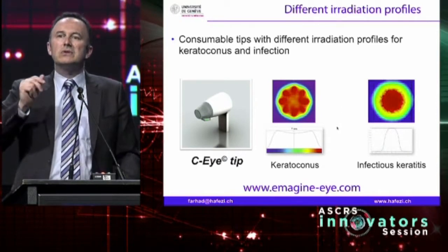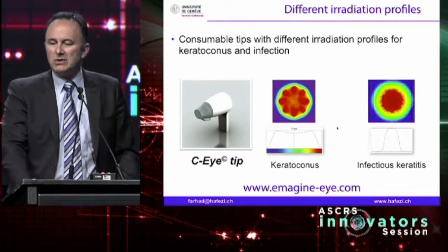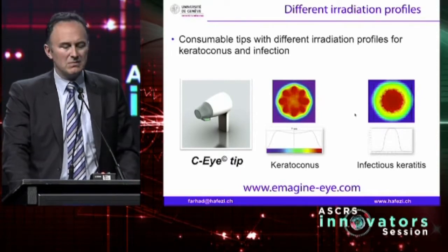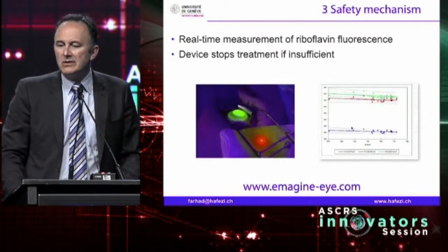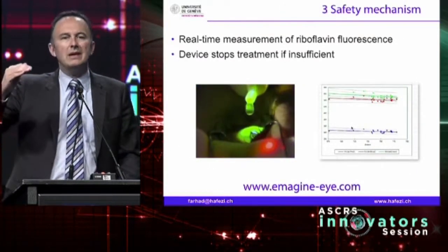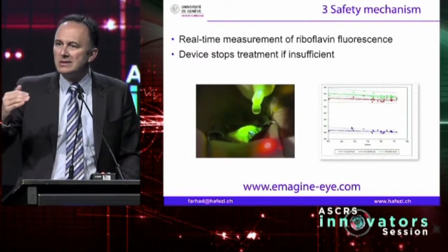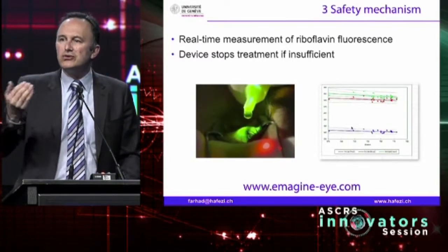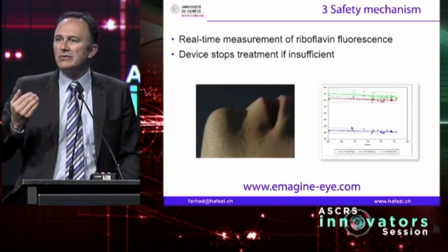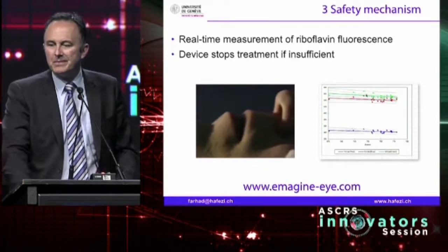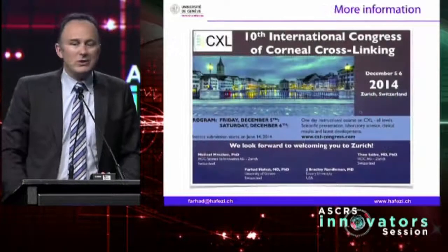And if we were to give this into the hands of the general ophthalmologist, we need a security mechanism. And this is the security mechanism. It is a real-time measurement of the fluorescence of the chromophore to ensure that there is proper saturation of the chromophore prior to treatment. Thank you very much for your attention.